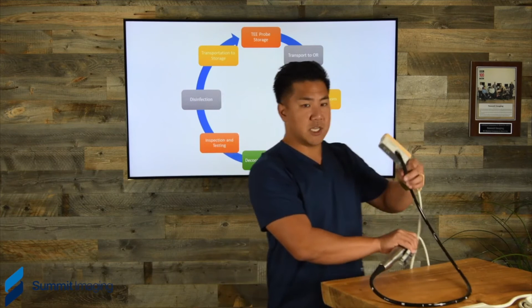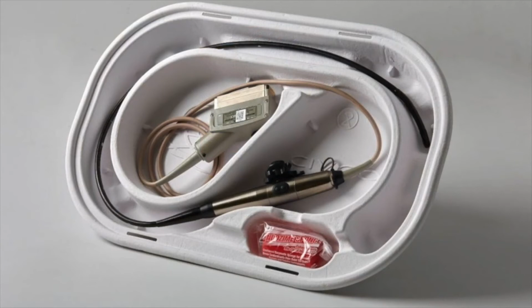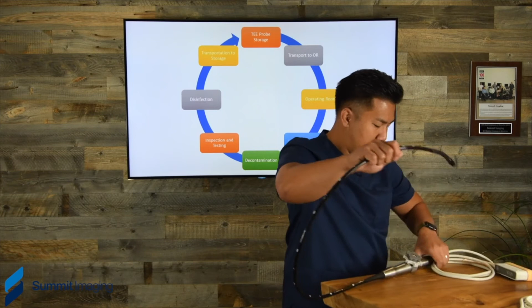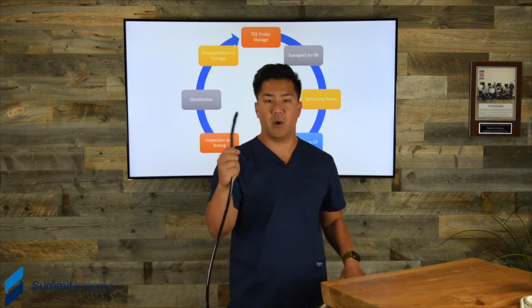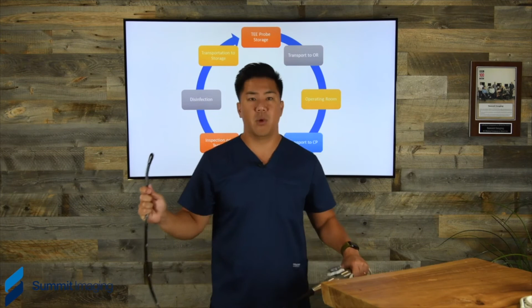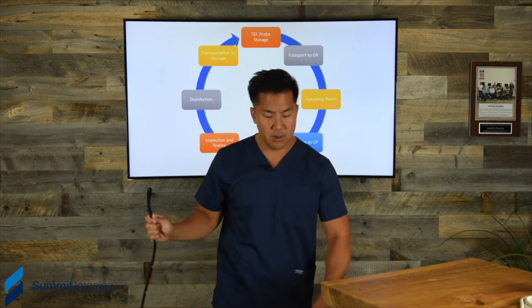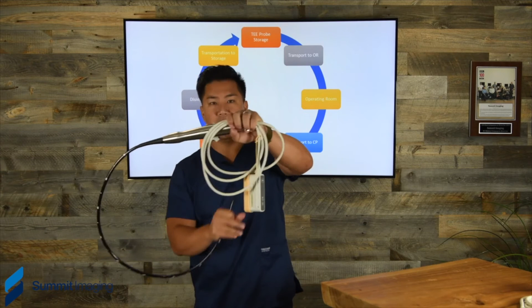We recommend getting a proper transport box for this. We've seen some nice totes. But if you really have to, we recommend grabbing the handle, coiling up the cable, and now holding this right underneath the tip with some gloves. This is a way to control all the heavy parts of this transducer, because the heavy parts are what's going to hit things, especially protecting this tip. So now you have full control of the tip of the transducer. You have control of the handle, and then this connector with a short leash here with your left hand or right hand will not swing around and bang things, especially keeping it away from the most sensitive part of the transducer, which is the TEE probe tip with the crystal on it.